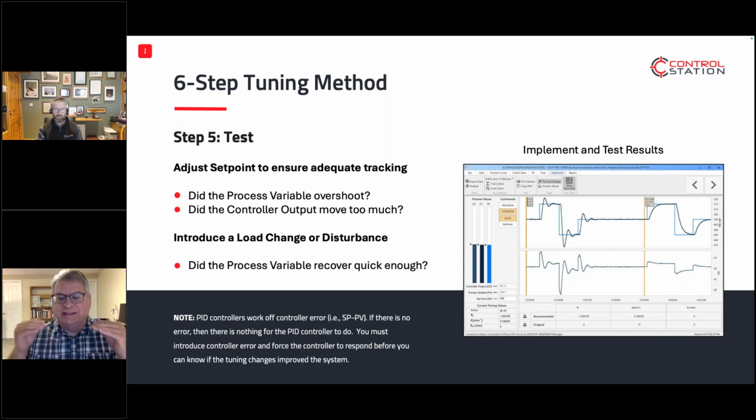We're just at the edge of capacity, or maybe over capacity, based on when the plant was built, so we don't want to overshoot. So maybe I want to tune this loop on the inside, the primary, so that I don't have overshoot. That's basically what I would do. I would set moderate tunings, and I would not have overshoot, as demonstrated on the second bump. So yeah, our software does certainly give you those two before and afters.